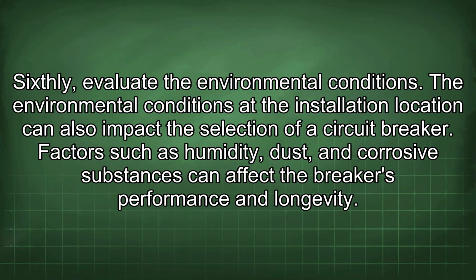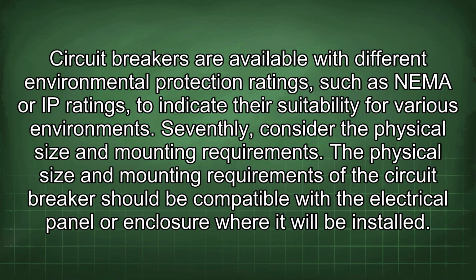Sixthly, evaluate the environmental conditions. The environmental conditions at the installation location can also impact the selection of a circuit breaker. Factors such as humidity, dust, and corrosive substances affect the breaker's performance and longevity. Circuit breakers are available with different environmental protection ratings, such as NEMA or IP ratings, to indicate their suitability for various environments. Seventhly, consider the physical size and mounting requirements.